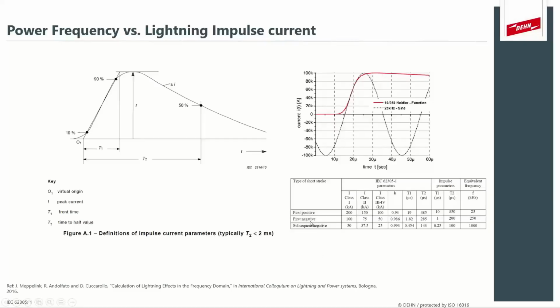90% of the strikes are characterized as first negative, meaning they carry negative charge, and the wave shape is completely different. So the rise time is much steeper, and the decay time is also a bit quicker. So if they then characterize that as a sine wave, it would be 250 kilohertz. Now, for this presentation, I decided to use the first negative in our calculations. As I said, this makes up 90% of lightning strokes. The subsequent negative is used to characterize subsequent strokes that occur after the first stroke. So when lightning actually strikes from cloud to earth, it ionizes a path from cloud to ground, and subsequent strokes will then follow on that ionized path. And that's the phenomenon where you see lightning striking and you see subsequent flashes as it strikes, but the lightning bolt or the lightning stroke stands completely still while flashing.